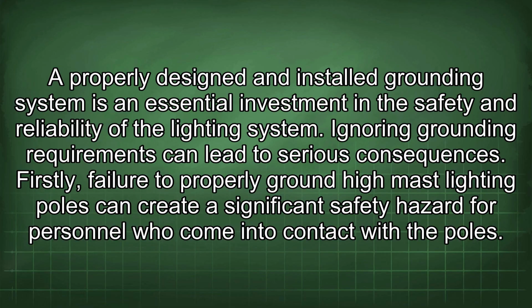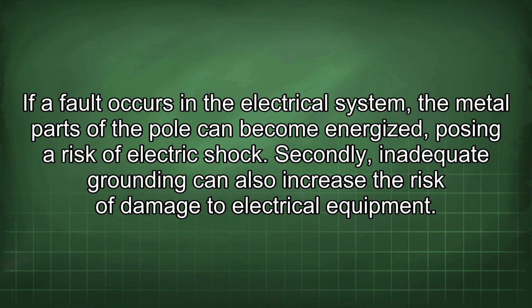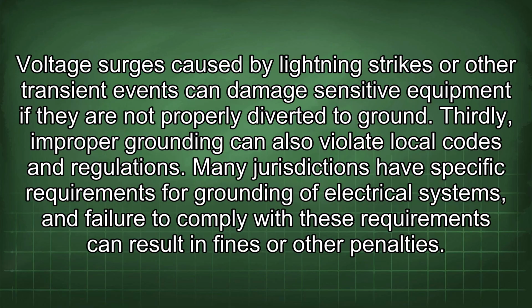Firstly, failure to properly ground high-mast lighting poles can create a significant safety hazard for personnel who come into contact with the poles. If a fault occurs in the electrical system, the metal parts of the pole can become energized, posing a risk of electric shock. Secondly, inadequate grounding can also increase the risk of damage to electrical equipment. Voltage surges caused by lightning strikes or other transient events can damage sensitive equipment if they are not properly diverted to ground. Thirdly, improper grounding can also violate local codes and regulations. Many jurisdictions have specific requirements for grounding of electrical systems, and failure to comply with these requirements can result in fines or other penalties.